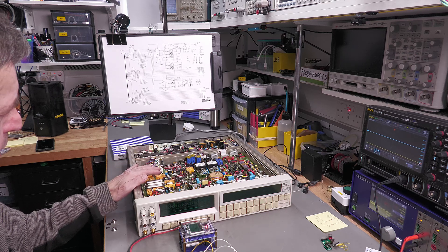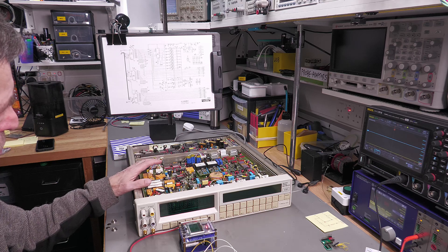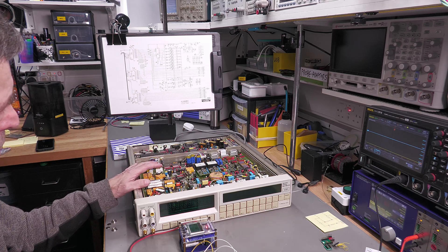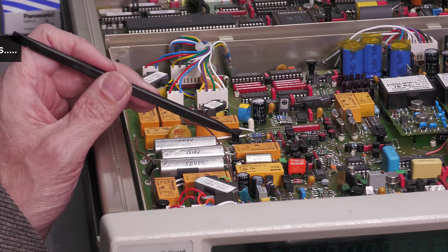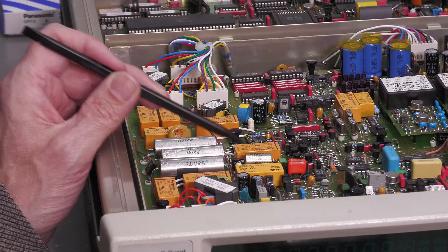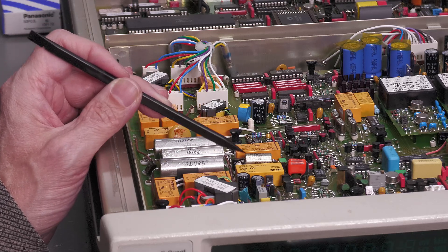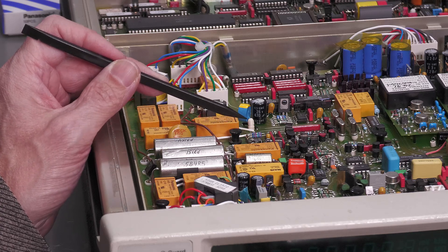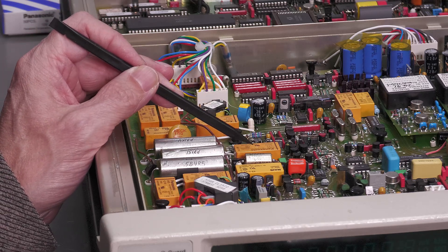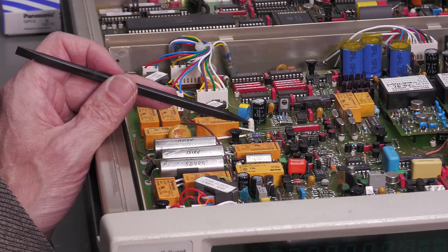Now although both types of relays are latched, the drive circuitry within the 1281 is only capable of driving one relay. The single coil latch relays originally fitted to the 1281 are actually quite hard to find replacements for, and probably hence why the Panasonic dual coil ones were fitted to the 1281 by the owner.